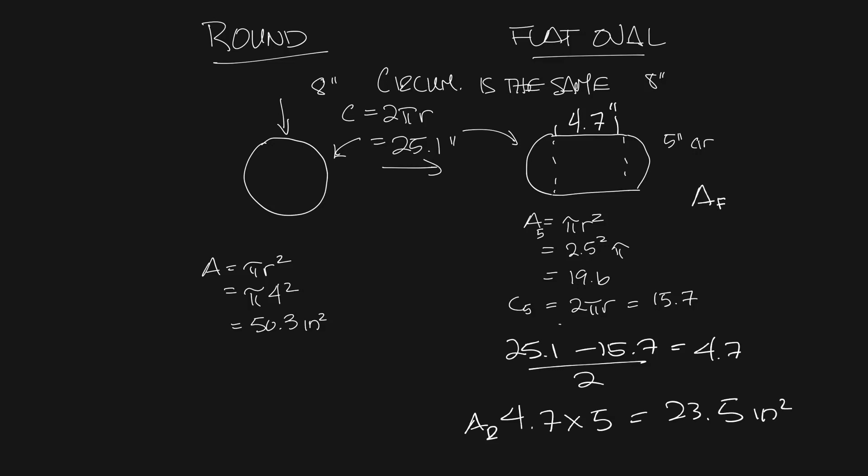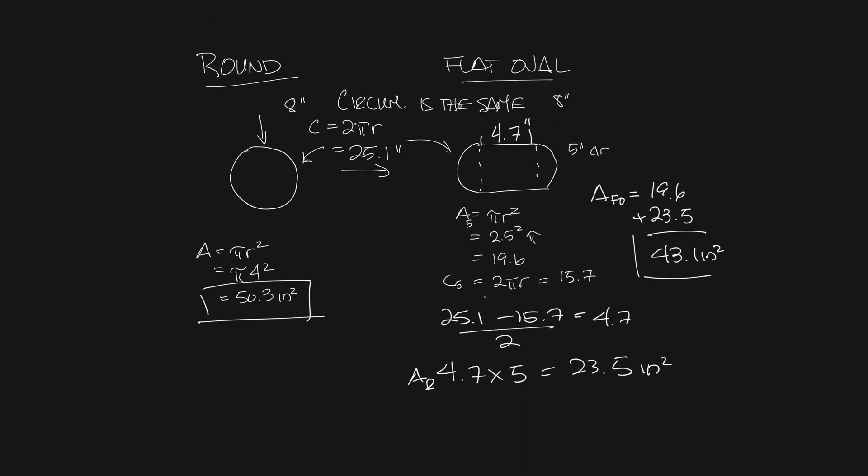So the area of the flat oval is 19.6 plus 23.5 is 43.1 square inches. Compare that to the 50.3 square inches of the 8 inch round.